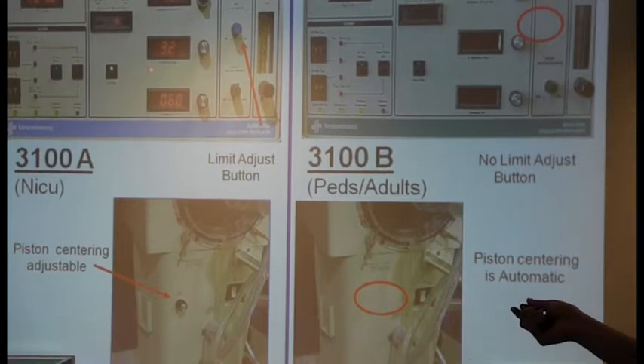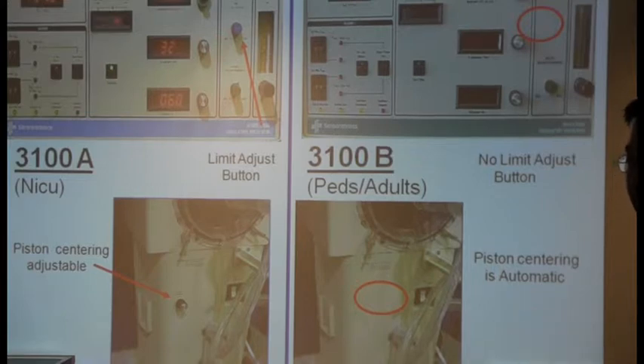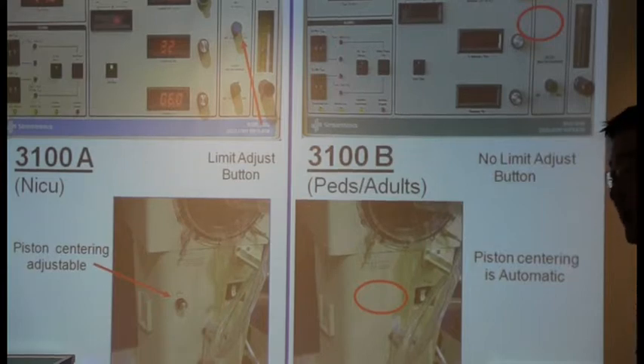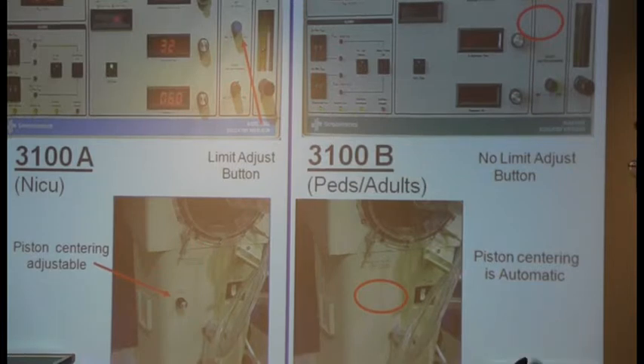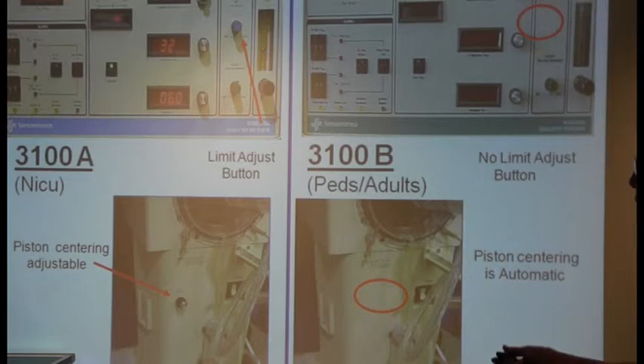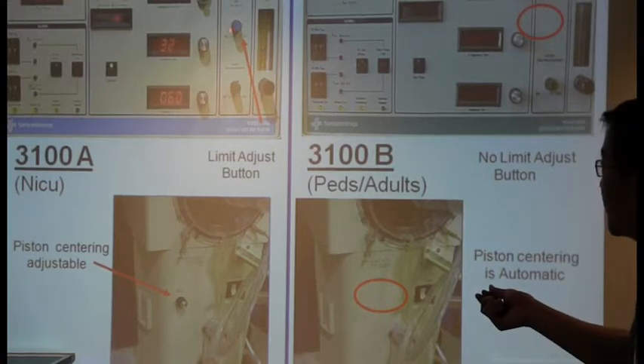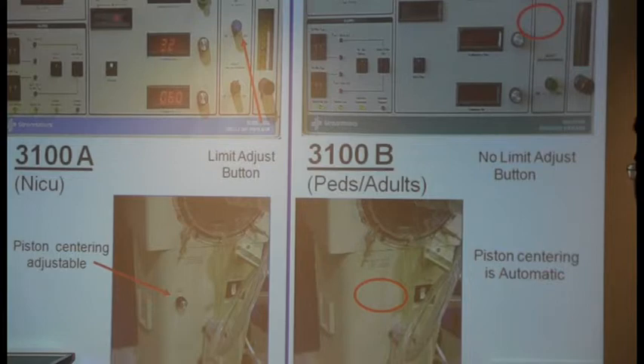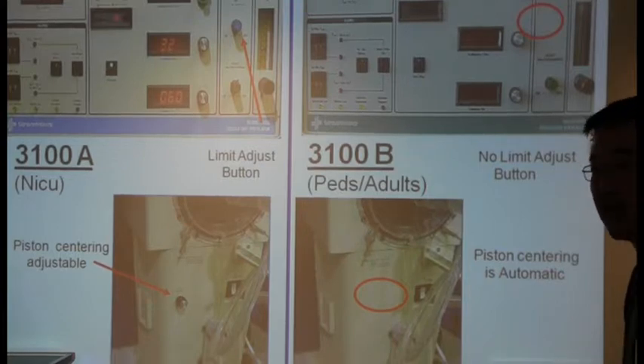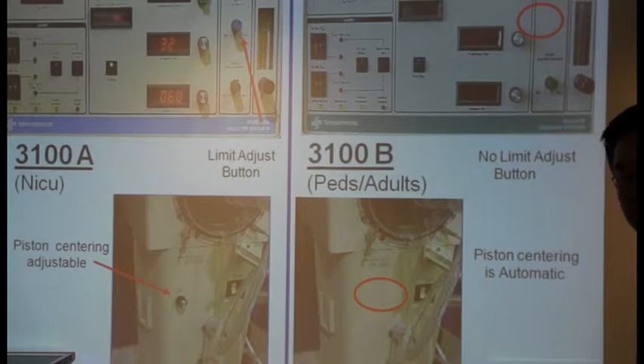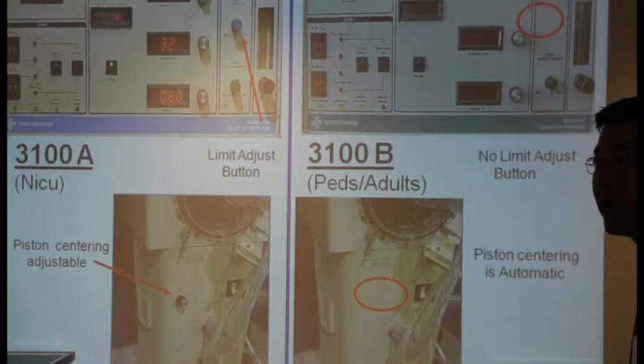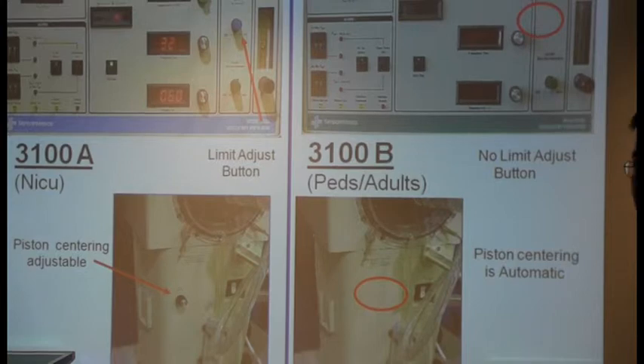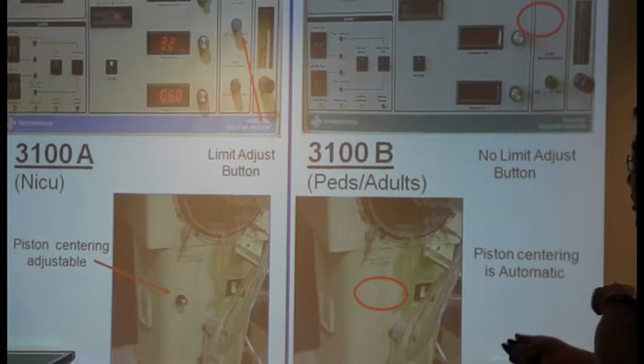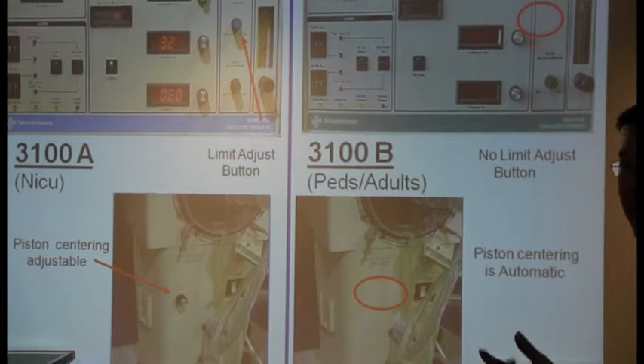So now that you've guesstimated to be about 23, how do you confirm where it's at? When you take your baby off to bag or suction or weigh, you turn your adjust all the way to max. Your number should go no higher than 23, where you set your limit. That's how you can confirm it. So next time you take the baby off, do that to see where you're at. People say, what are you doing? Oh, I'm just checking my limit, popping off where it's at, as a safety. So now you just turn your adjust back to 21, where it's supposed to be, put the baby back on, and you're good to go.